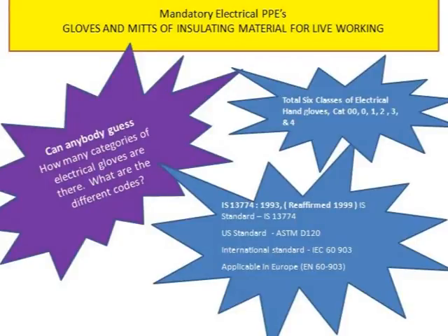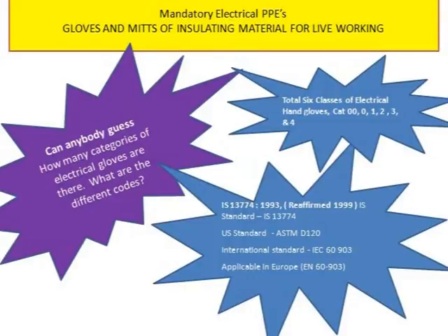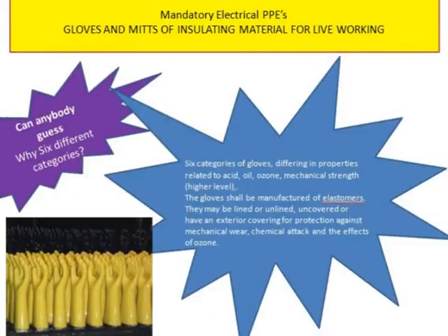There are total six classes of electrical hand gloves: category double zero, category zero, category one, category two, category three, and category four. Different standards exist, such as IS 13774 from 1993, the US standard ASTM D120, and the international standard IEC 60903, which is applicable in Europe as EN 60903.